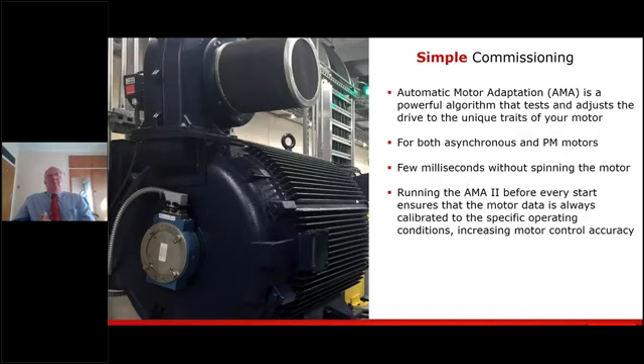Now, Danfoss uses a system called automatic motor adaptation, and this is what we would call an auto tuning procedure, and it's recommended to be carried out during the commissioning phase. And what that does, it ensures that the VSD is matched to the motor and the installation. This then ensures we get optimum performance with improved overall system efficiency. It ensures that the motor runs quieter, you don't get that humming noise, and it is a quick and simple commissioning. And it also ensures that the cable between the variable speed drive and the motor is actually compensated for.